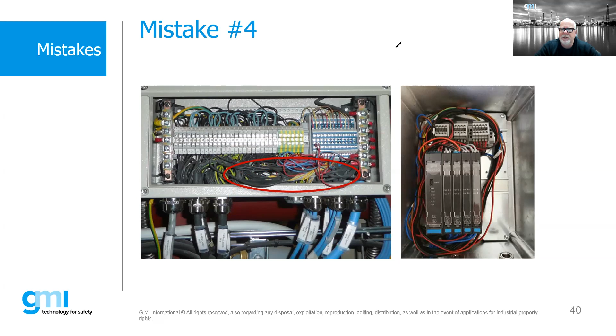The same thing holds true when we look at this particular installation, right? We have our protection from our IS going out. We have our incoming power. But what we have done, we have looped our power cables all the way around. So we've defeated our 50 mil separation. So we want to make sure that when we're using IS, we have segregation between IS and non-IS.